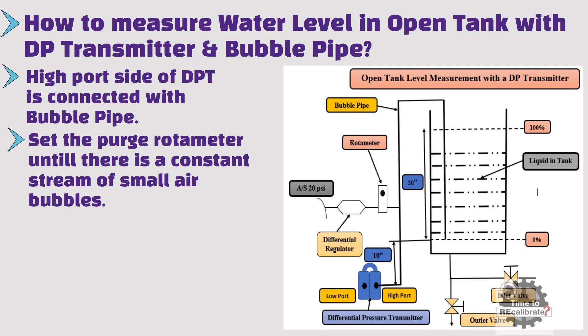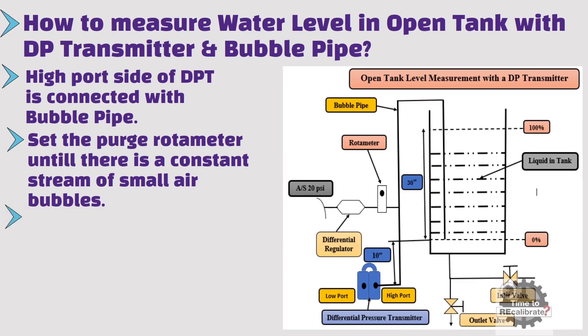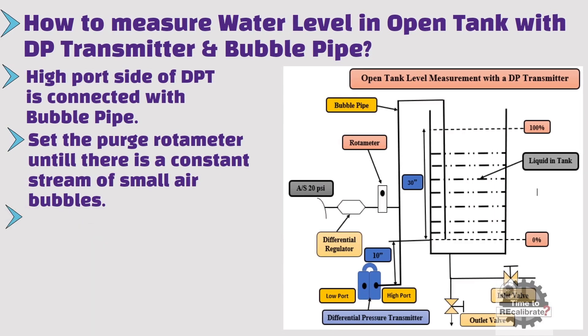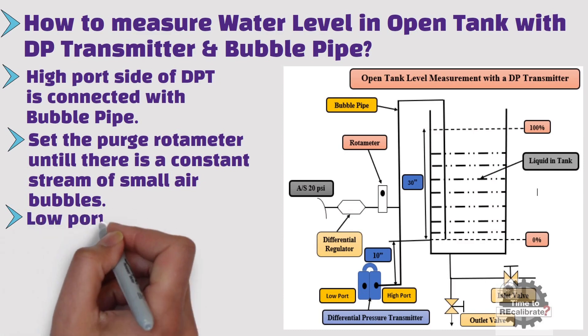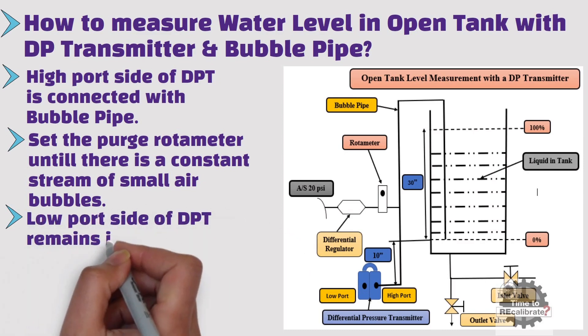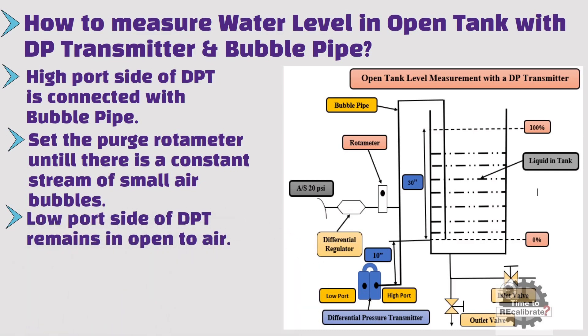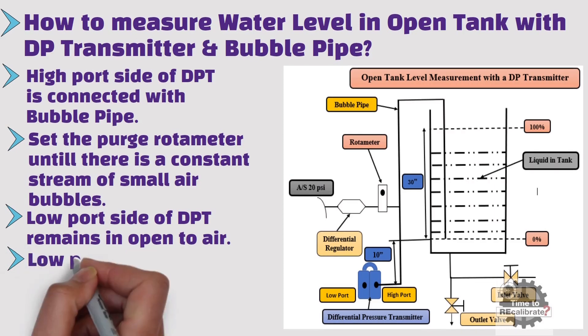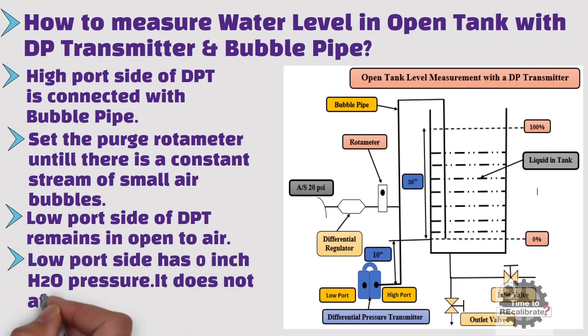So, even though the transmitter is installed 10 inches below from the 0% baseline, it does not affect the calibration range. As you can see from the picture, the low port side of the DPT remains open to air — in other words, it does not connect with anything. Therefore, the low port side has 0 inch H2O pressure, and it does not affect the calibration range.